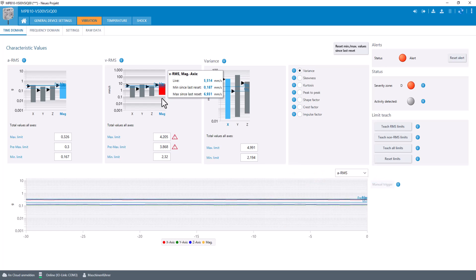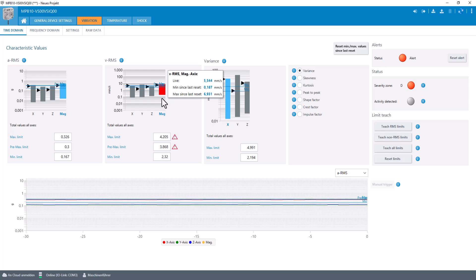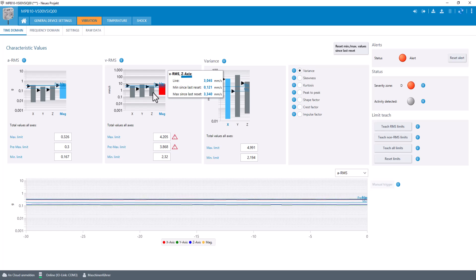As the MPB10 is a tri-axial sensor, the direction where the change is coming from can be identified. So the vibration is mainly occurring in radial and not in axial direction.